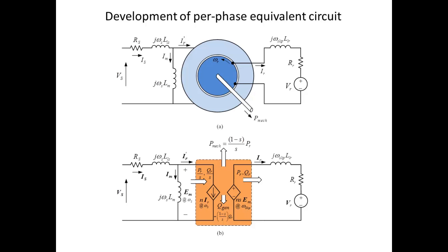Keep in mind that S — at least in the case of induction machines operating as a motor — is a very small value, like a slip of 3%, or S = 0.03. In the case of the DFIG, S is not always a very small value. It actually covers a wide range from positive 0.2 or 0.25 to negative 0.2 or 0.25, which corresponds to the range of speed variation possible in the DFIG machine.